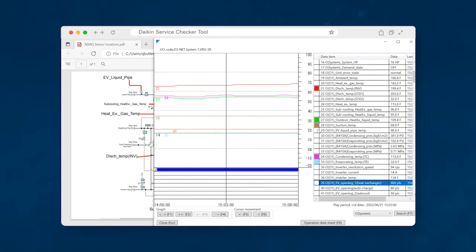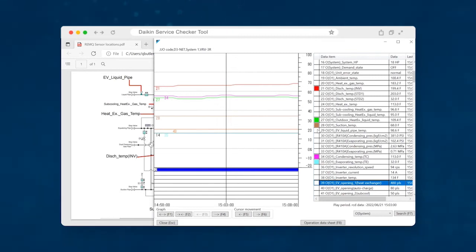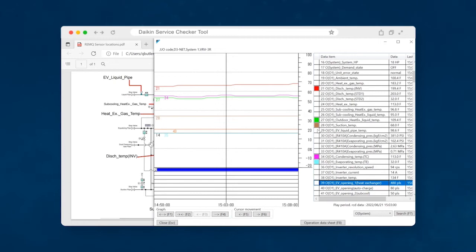And your discharge superheat will be way out of range. And so, if you have adequate suction superheat coming back, you're cooling the compressor with enough cool refrigerant to keep the winding temperature down under normal circumstances, assuming that you had enough oil. But if you don't have enough oil in the sump of the compressor, you have that added friction. Added friction obviously creates heat and that's where your discharge superheat becomes elevated.